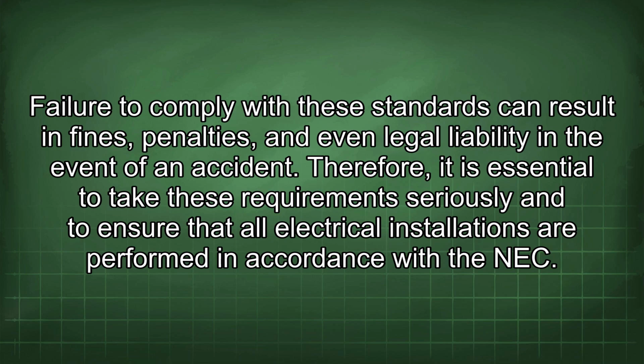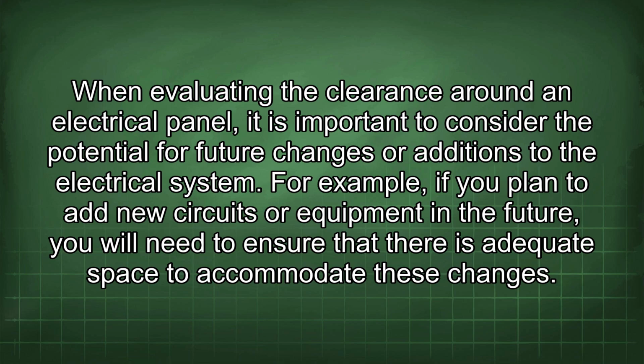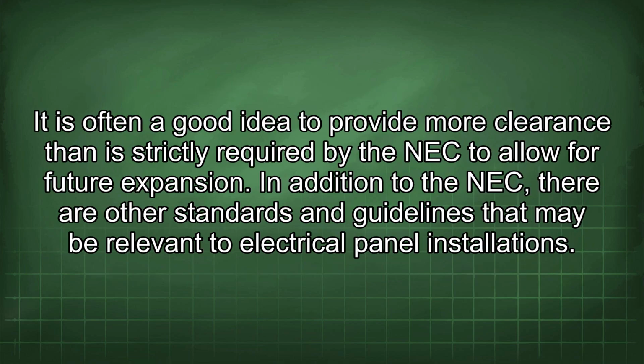accordance with the NEC. When evaluating the clearance around an electrical panel, it is important to consider the potential for future changes or additions to the electrical system. For example, if you plan to add new circuits or equipment in the future, you will need to ensure that there is adequate space to accommodate these changes.